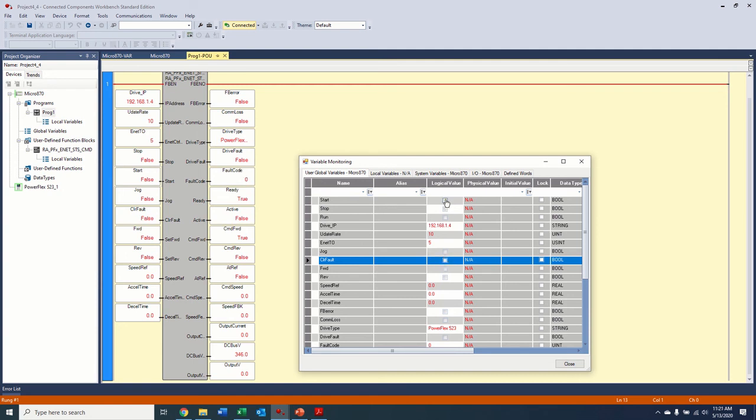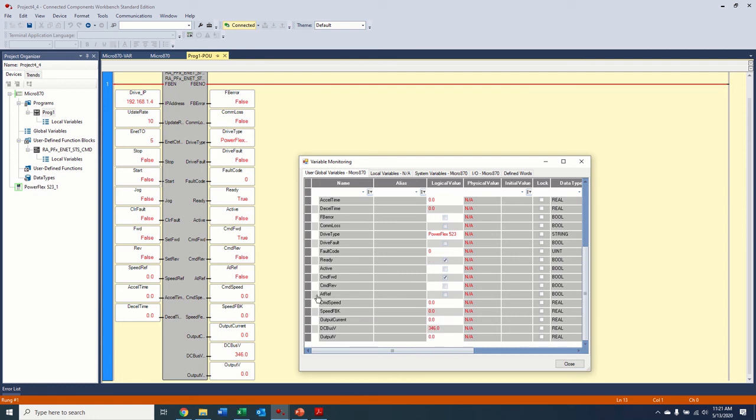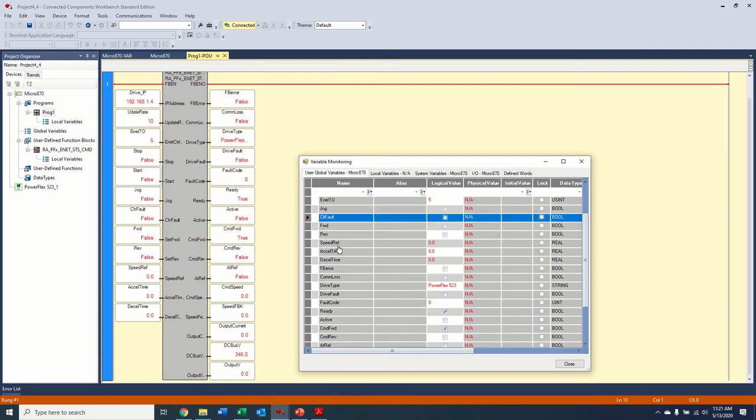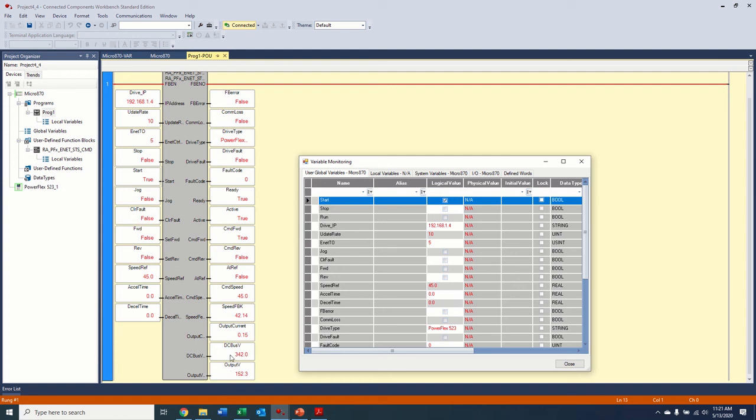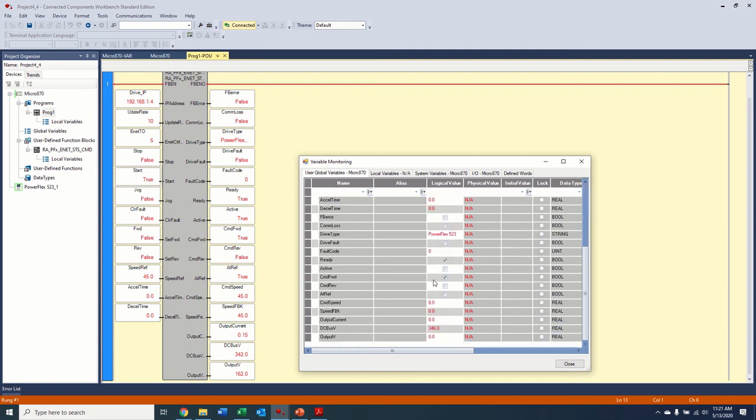So again, our fault code goes to zero. Our drive isn't faulted. So let's try, first of all, before we get too far ahead, let's give it a speed reference here of 60 hertz, or we'll do 45. So then we'd see 45 in our speed reference. Let's start. And okay. So our output voltage, we're seeing output current. And there's our speed feedback. We are at our reference. We're getting all the information live from back of the drive. And we're doing it at a 10 millisecond update rate. That's what our update, you can slow that down or speed it up as your network will allow you.